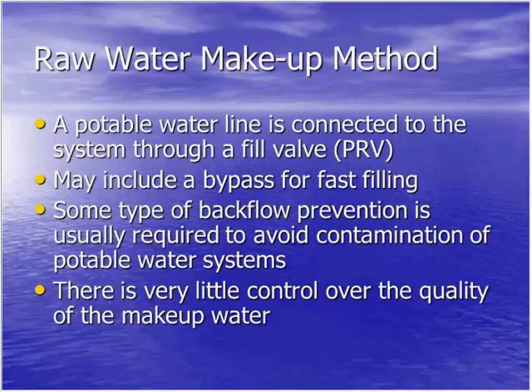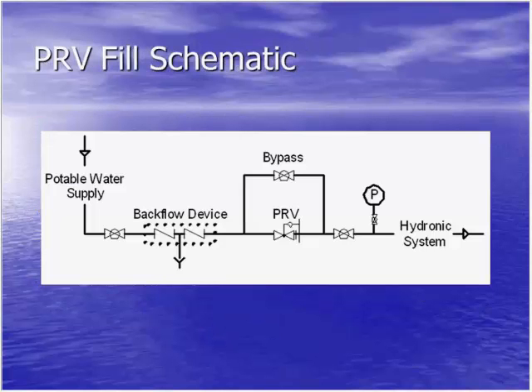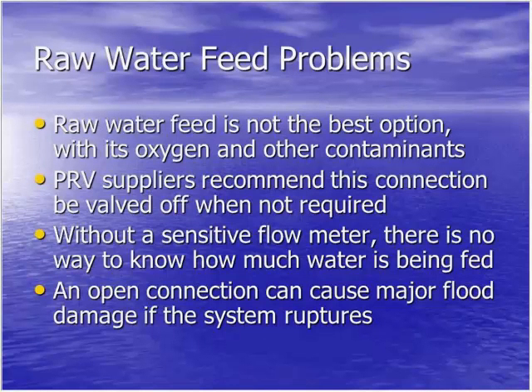Here's just a basic schematic. As I mentioned, potable water supply, backflow prevention device, pressure reducing valve. In some instances, commercial instances, they put in a bypass to fast fill or purge the system. So it's all those components and the associated piping that's tied into a hydronic system that typically maintains pressure. And there's issues with this method. Raw water feed's not the best option because, as we talked about before, oxygen and the other contaminants that are in the water are introduced into the system.